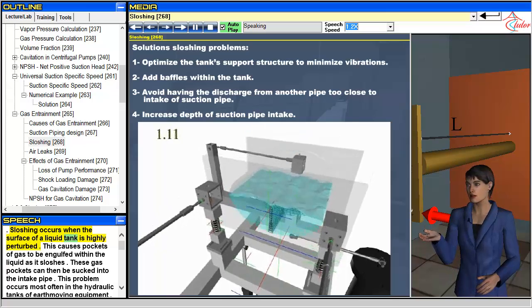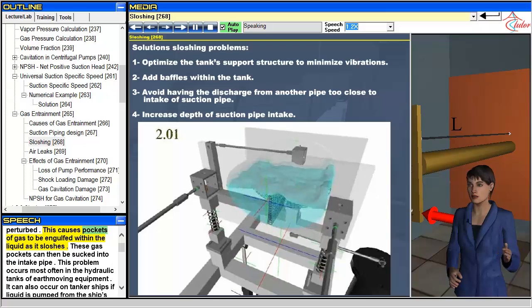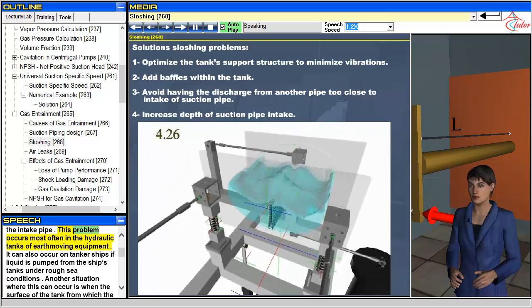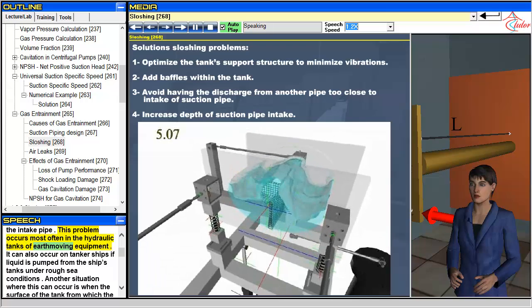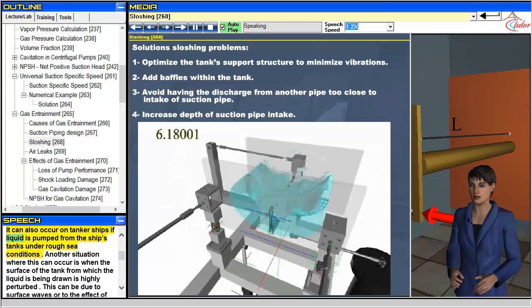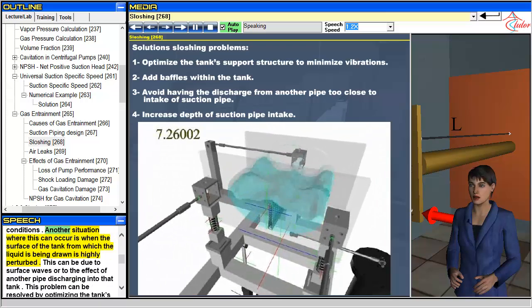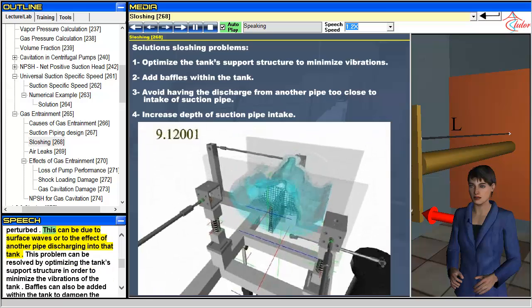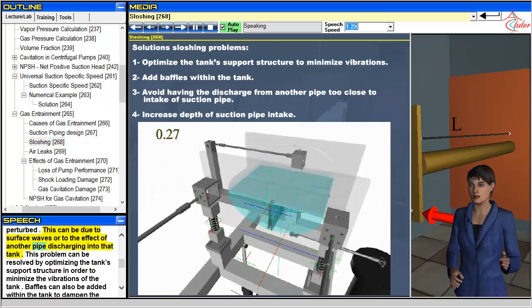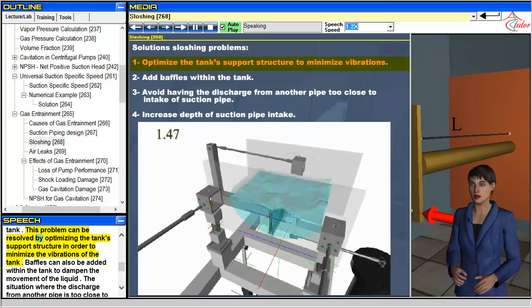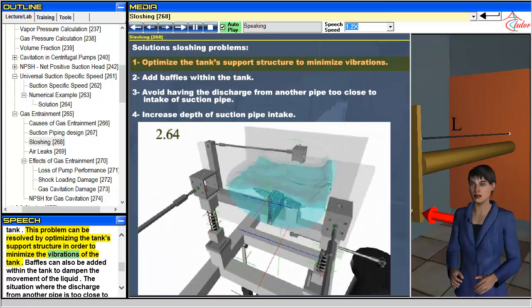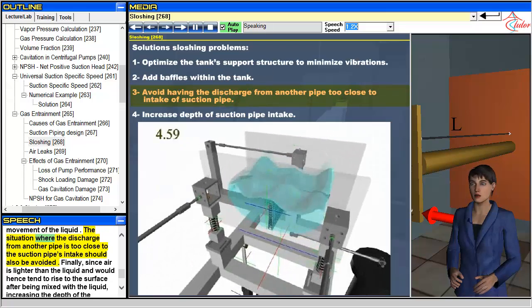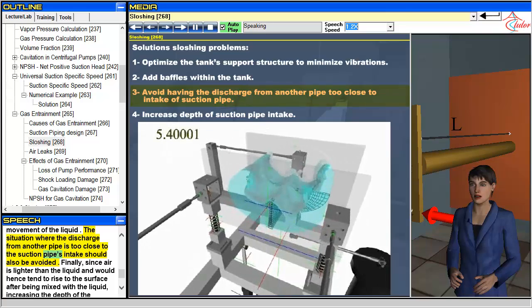Sloshing occurs when the surface of a liquid tank is highly perturbed. This causes pockets of gas to be engulfed within the liquid as it sloshes, and these gas pockets can then be sucked into the intake pipe. This problem occurs most often in the hydraulic tanks of earth-moving equipment. It can also occur on tanker ships if liquid is pumped from the ship's tanks under rough sea conditions, or when another pipe discharges into that tank causing surface perturbation. This problem can be resolved by optimizing the tank's support structure to minimize vibrations, and by adding baffles within the tank to dampen liquid movement. The situation where the discharge from another pipe is too close to the suction pipe's intake should also be avoided.